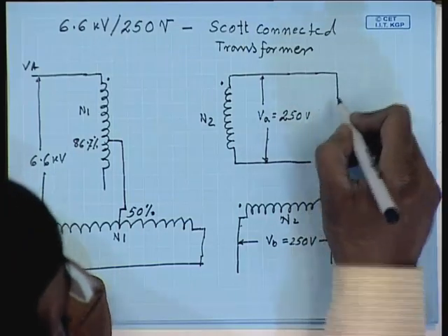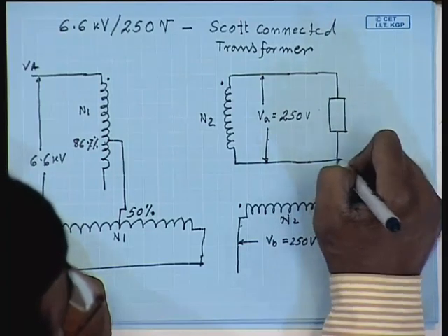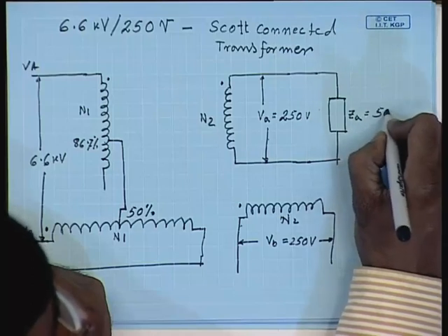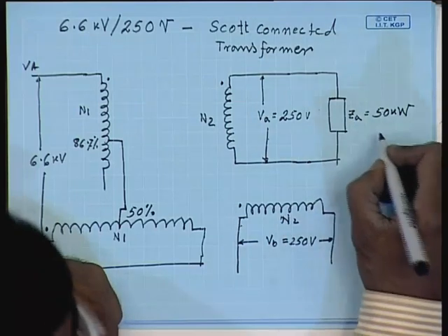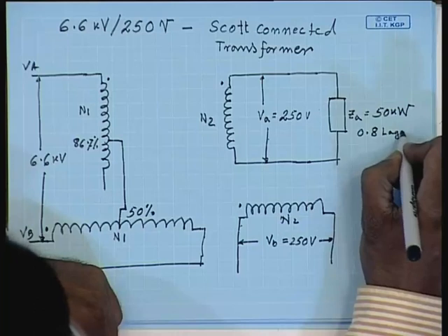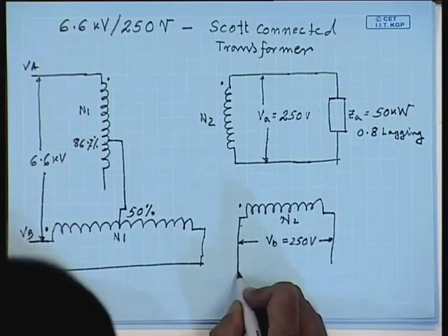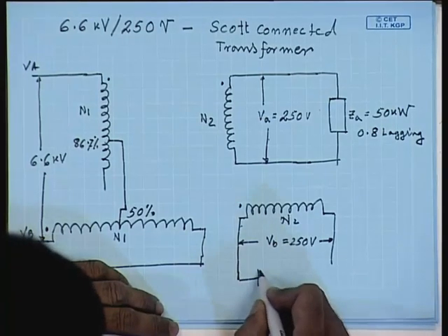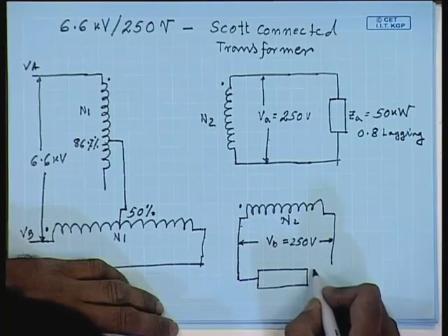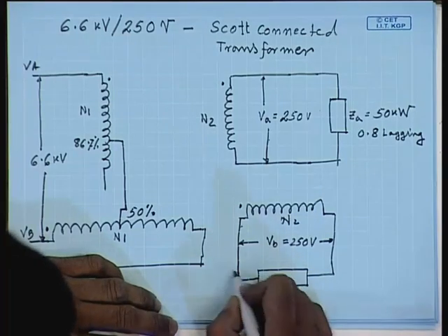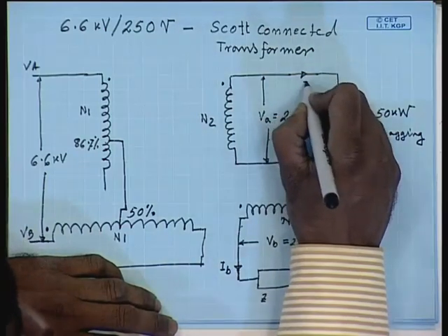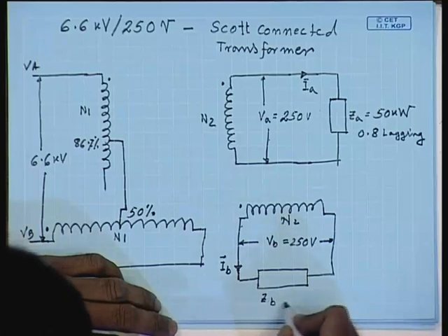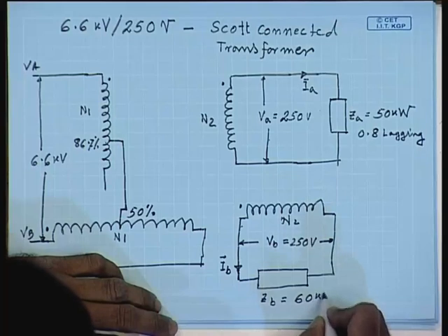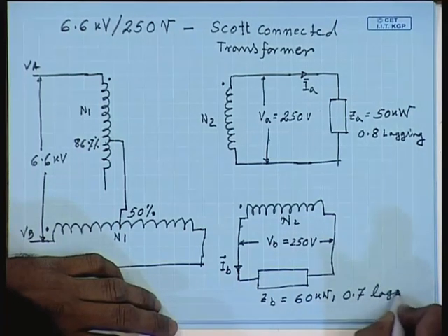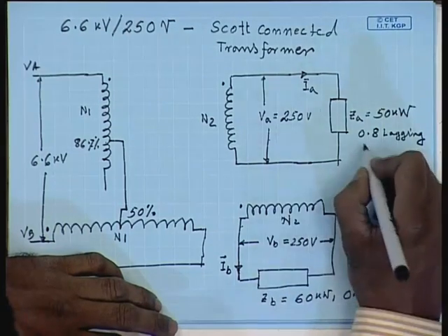Now the load on this transformer on the leading phase, that is on phase A, I have connected a load ZA, which is equal to nominally 50 kilowatt, that is when the voltage is 250 volts, it is 50 kilowatt at 0.8 lagging power factor. And I have connected another load ZB to the lagging phase, this current is IA, this current is IB, equal to this is 60 kilowatt at 0.7 lagging power factor, that is the load is unbalanced.